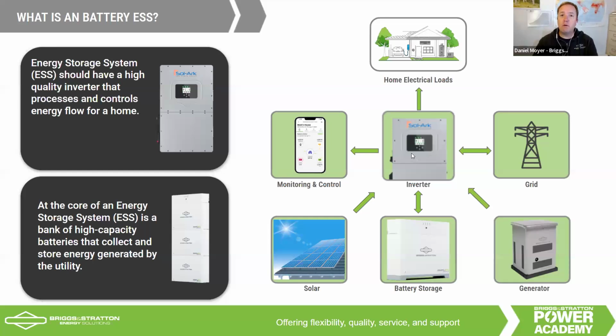Of course, we can also bring in generators. And I'd argue, Bo, that in places with large air conditioning loads, generators still may play a role. What we can do is, as the battery starts to run low, the inverter recognizes the state of charge is dropping, so we start up the generator. We run the generator hard, near its max load, at its most fuel-efficient run point.